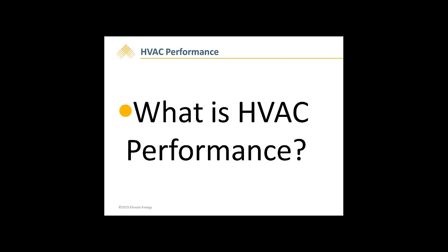So what is HVAC performance? Unfortunately, the industry hasn't settled on standard language. Sometimes it's called commissioning, system efficiency, right sizing, or performance tune-up. By any definition, HVAC performance recognizes that real efficiency does not equate to rated efficiency. In fact, that real efficiency is something less than rated efficiency. I've seen many furnaces that were rated 95% AFUE that were operating at less than 70% system efficiency. HVAC performance also recognizes that the contractor has an impact on real efficiency.